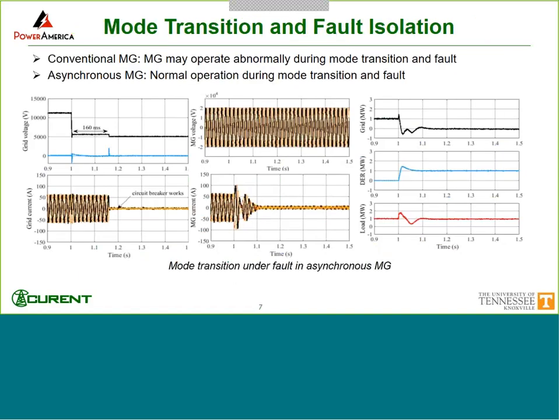This is an example of mode transition. Let's say there is a fault on the grid side, and you would have to transition to the islanded mode. On the grid side, you will see the voltage start to drop and power start to drop and circuit breakers start to act. But on the microgrid side, you pretty much don't see any changes. The power will simply transfer from the grid to the distributed energy resources, in this case like energy storage or a backup generator. So that will allow a pretty seamless transition.